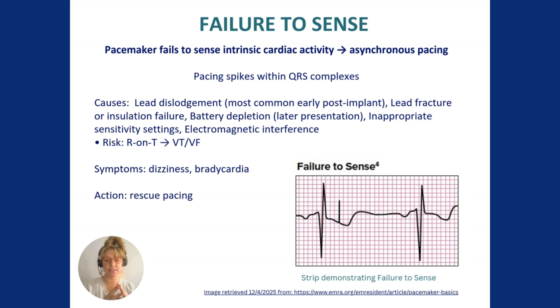Common causes include early lead displacement, incorrect sensitivity settings, lead fracture, or electromagnetic interference. Clinically, patients may report dizziness, palpitations, bradycardia. Nursing priorities are immediate assessment, continuous monitoring, urgent notification to cardiology. We're going to apply pacing pads if the patient is unstable. So, key reminder for failure to sense: spike at the wrong time equals failure to sense, and it needs prompt escalation.